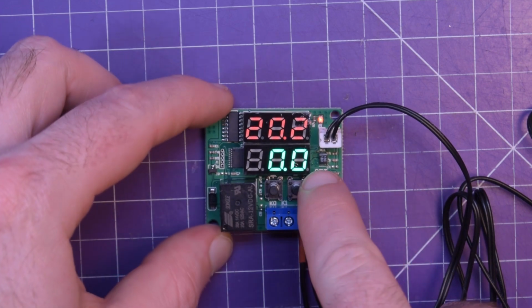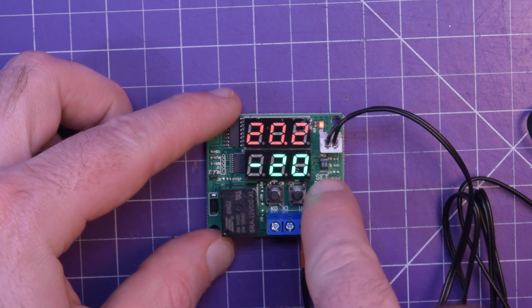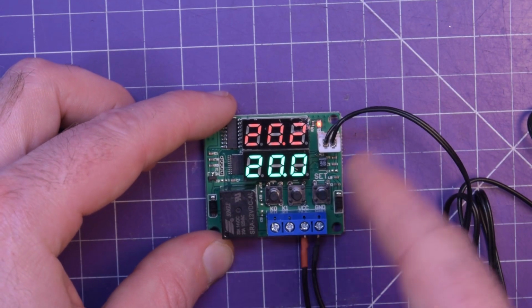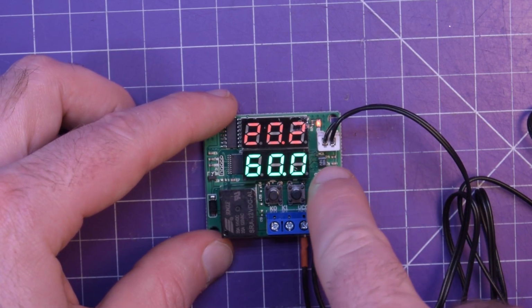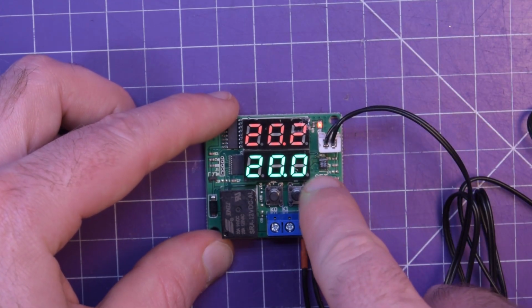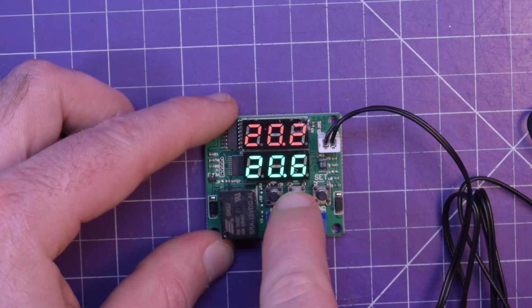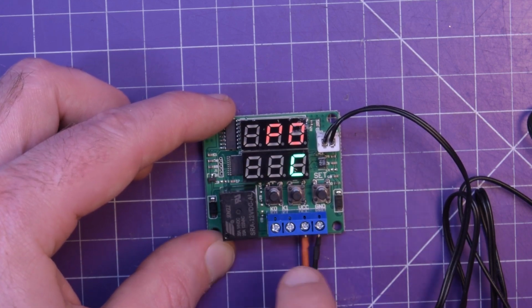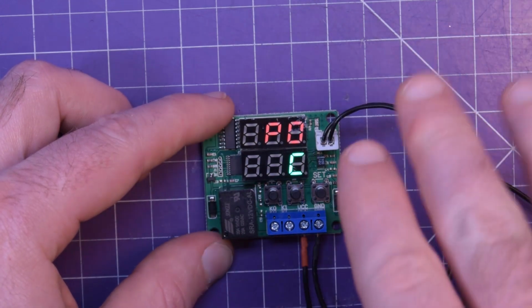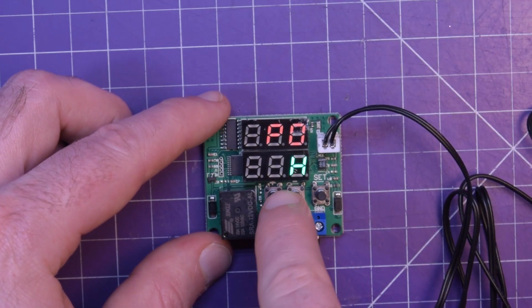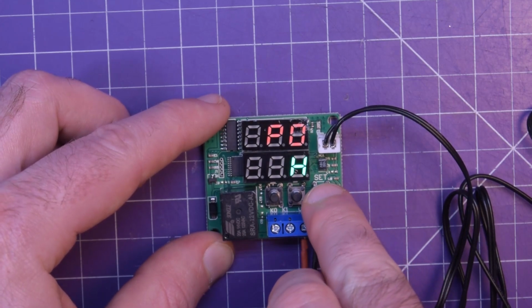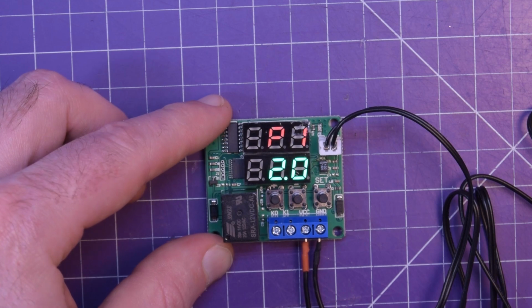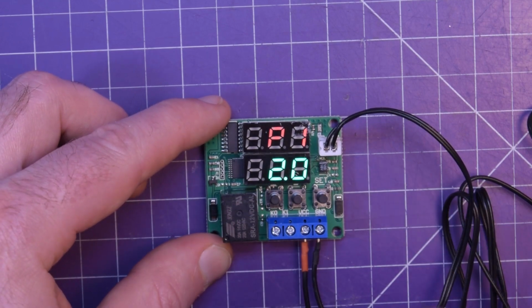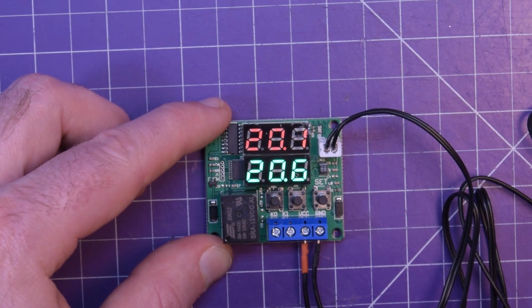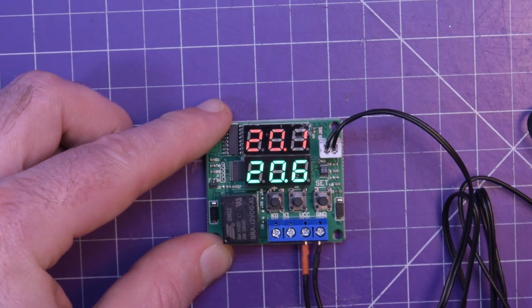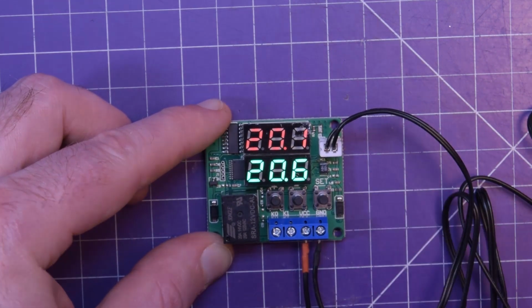Okay, I checked out the website. First of all, just pressing set moves the set temperature really quickly through a bunch of commonly used settings the board has been programmed with, so it's faster to adjust, but you can also use these buttons to adjust it manually. Then if you press and hold set, you get a bunch of menu options. You've got cooling and heating on P0 - cooling means it'll be on above the temperature that's set, heating means it'll be switched on below the temperature that's set. P1 is the hysteresis - so if it's on heat, it'll heat up until it hits 2 degrees over the set point in this case, and then it'll shut off, or vice versa. Anyways, 2 degrees of hysteresis.